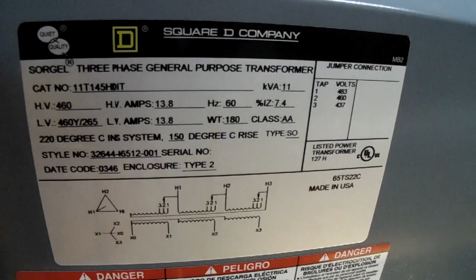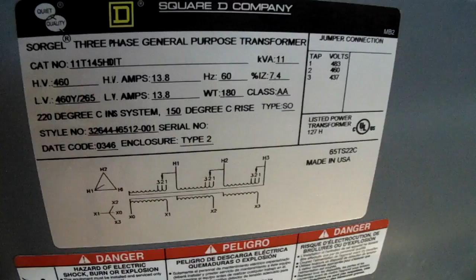So, if we have a look here at the nameplate, I'll let y'all focus on that for a second. Okay, you can see that is wired in a star and delta configuration. 11 kVA, 13.8 amps in and out. And I don't want it to be in a delta configuration anymore, because it is a three-phase transformer, but I'd also like to use it for single phase as well when I need to. So I thought of this.